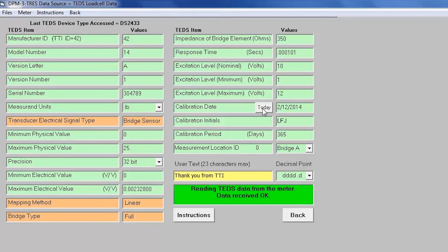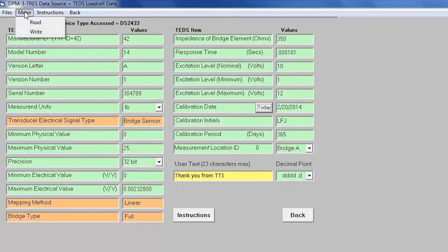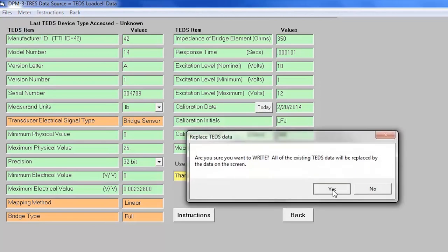Now we'll click on today to change the calibration date. From the control bar, click meter, then click on write to write the new template parameters to the EEPROM.